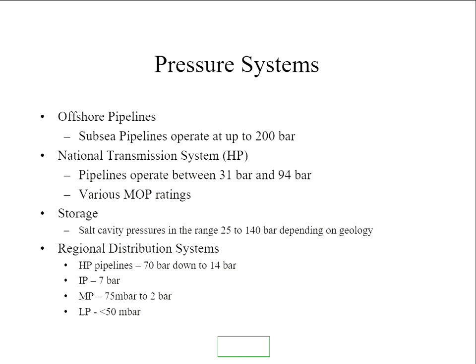And then once you get into the regional distribution systems, you've got anything from some higher 70 bar pipelines down to 14 bar, what they'll call intermediate pressure, 7 bar, which typically comes towards a city edge. Medium pressure, your bulk local distribution, but you will get that in populated areas, and eventually the low pressure mains, 50 millibar and below. So you've got a good old range of pressure regimes there, and a lot of the pressure control devices we'll talk about are about protecting downstream systems from upstream systems.